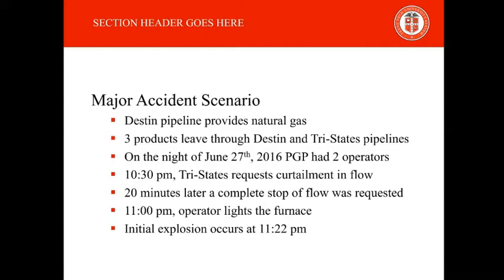Due to the limited storage capacity at Pascagoula gas plant, they needed to completely stop their natural gas liquid production. Part of the normal shutdown procedure is to manually light a burner on a hot oil furnace to add more heat to the demethanizer column. The resulting heat allows more natural gas liquids to vaporize and become part of the gas streams, rather than being sent to the bottoms as natural gas liquids.